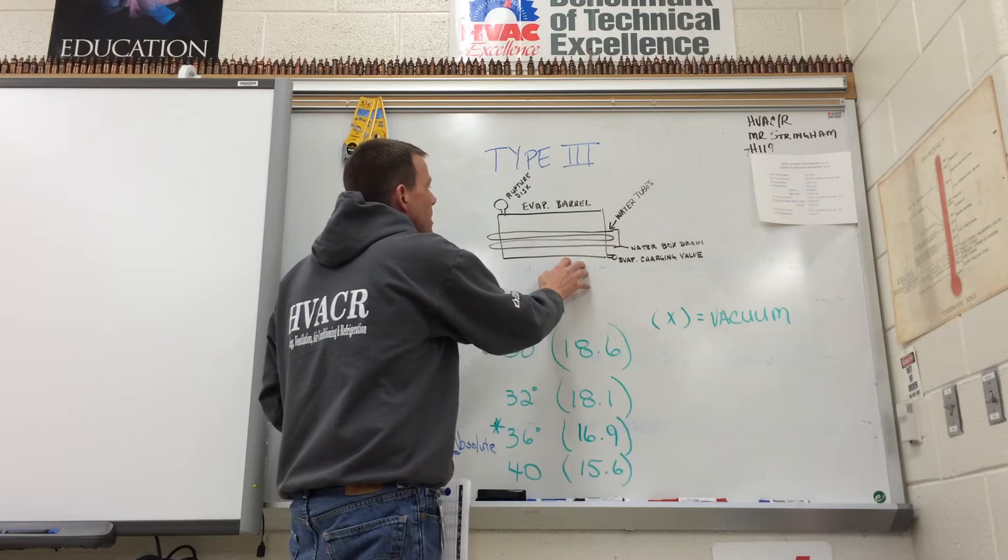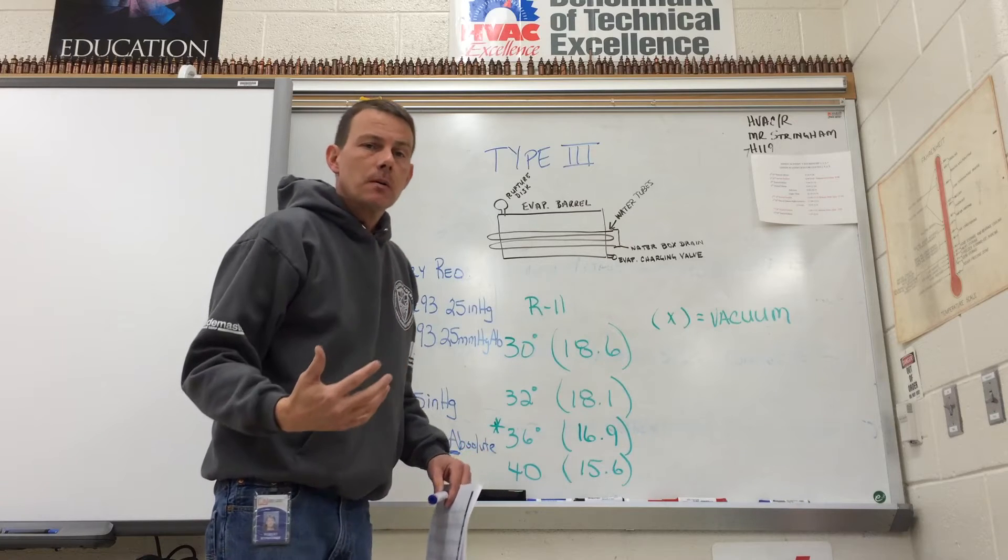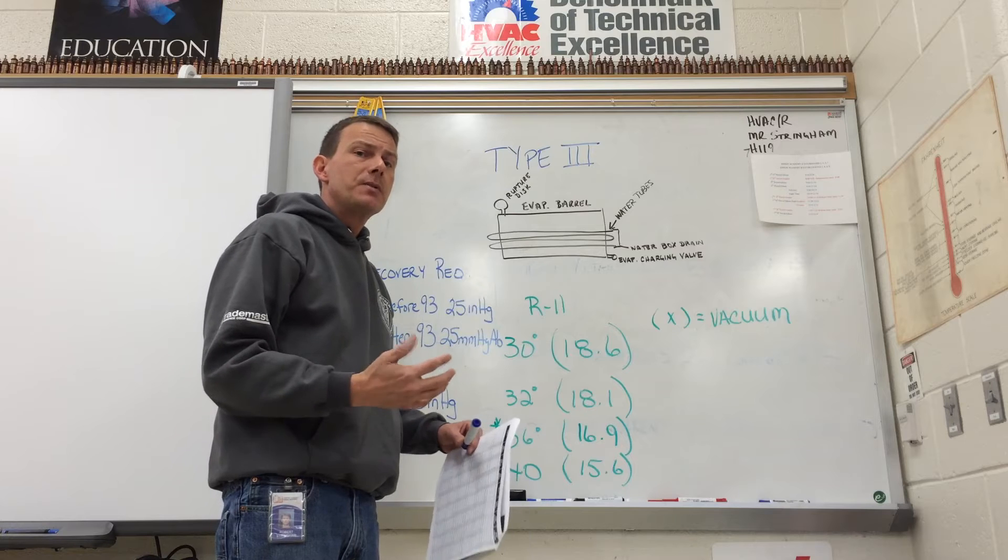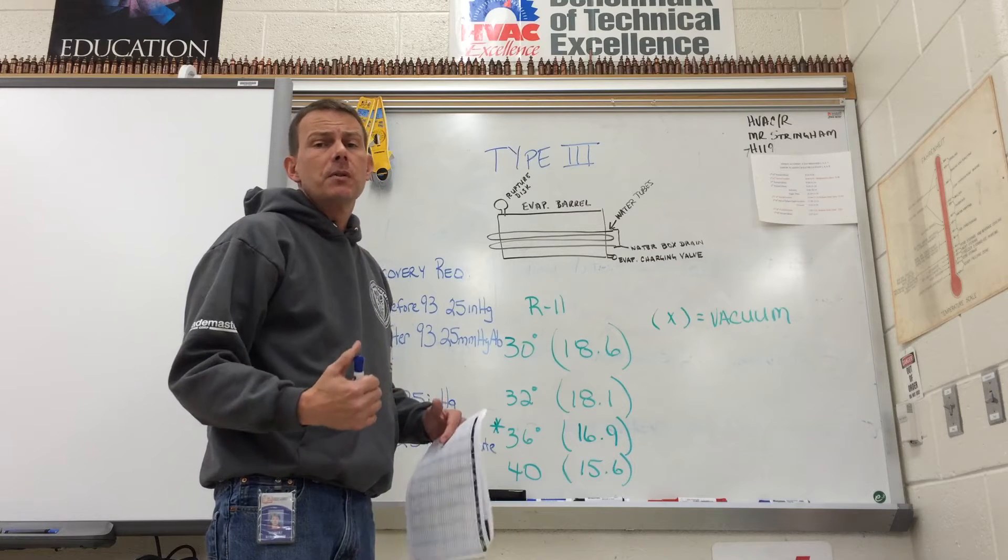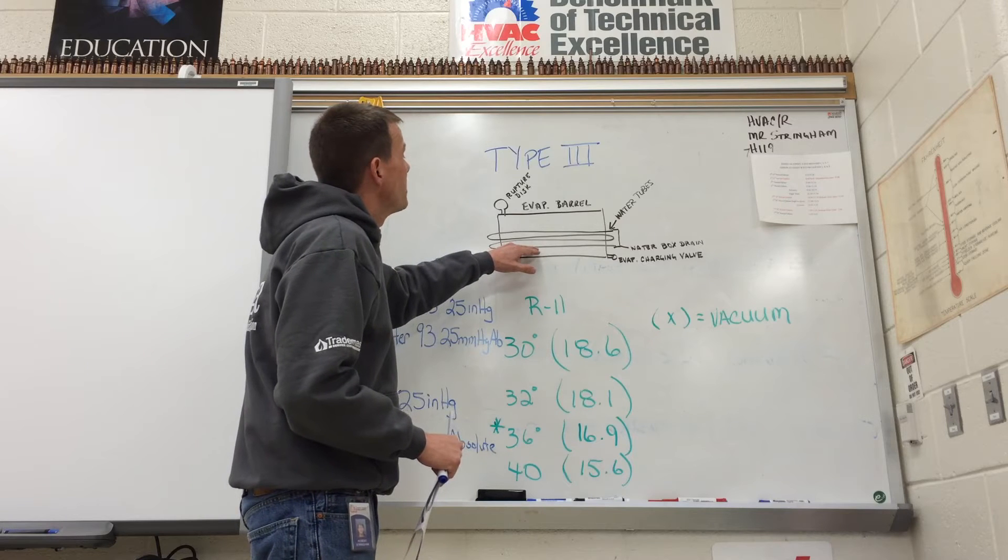And then the evaporator charging valve is where they would add the liquid refrigerant, but they want to make sure that people know that before you add liquid, you want to raise the pressure of the refrigerant up above 32 degrees so that it could keep the water in the pipes from freezing.